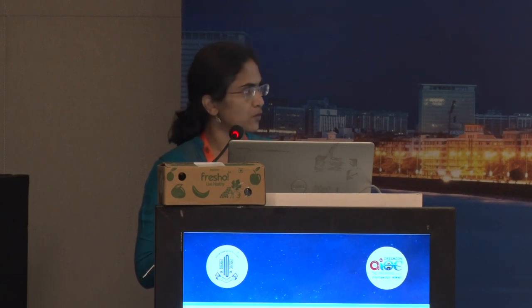So this is our Smart KC, which you can see there, which I have depicted. And here we had a lot of teething problems. The first was which Placido is designed to take. We are all aware there are three types: planar, ellipsoid, as well as the conical. We know the ellipsoid and planars will not occupy the whole of the cornea. So eventually we narrowed down to a conical Placido head with 28 rings and a 70 millimeter radius. So this is what we took as the Placido ring, and we went ahead with the conical well-fitting one.